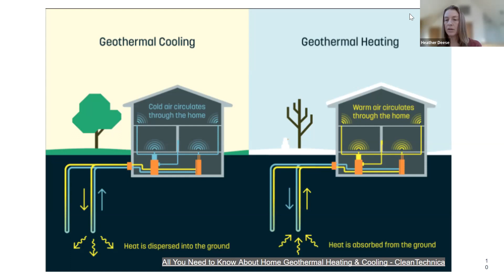So why is geothermal so helpful? One reason is that the cost of operating it is lower than any other form of heating. The US EPA has analyzed all the different types of heating systems in the US and identified geothermal as having the best environmental footprint and the lowest operating cost for customers. The issue with geothermal is the upfront installation cost, but once that loop—horizontal or vertical, like the one I showed—is in the ground, that system works for you, with a loop lifetime usually between 50 and 100 years.